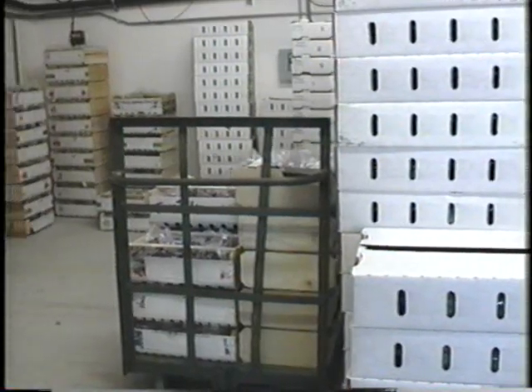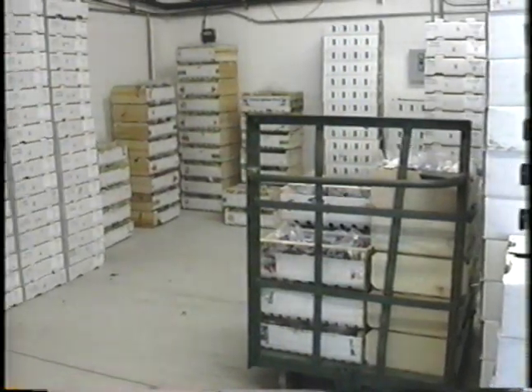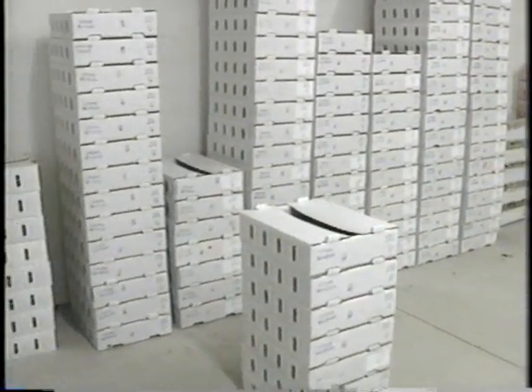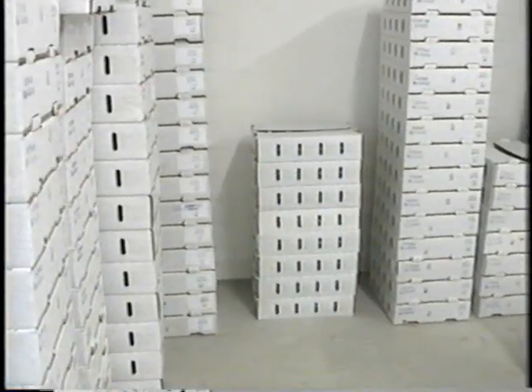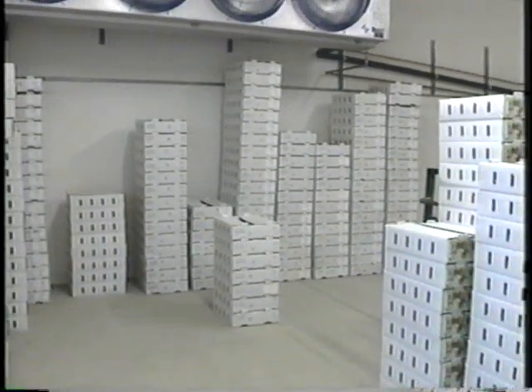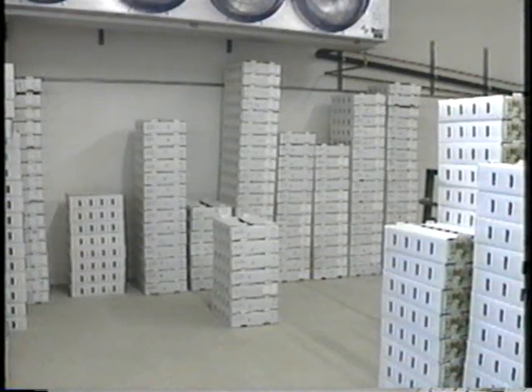The first consideration in building your own cold room is determining size. Floor area needed is based on the greatest amount of product you plan to hold at any one time. Review daily production records over the last few years to estimate the number of boxes needed. Boxes can often be stacked six feet high to reduce floor area. Also plan for expansion — it may be less expensive to build slightly larger now than to move walls and add refrigeration capacity later.